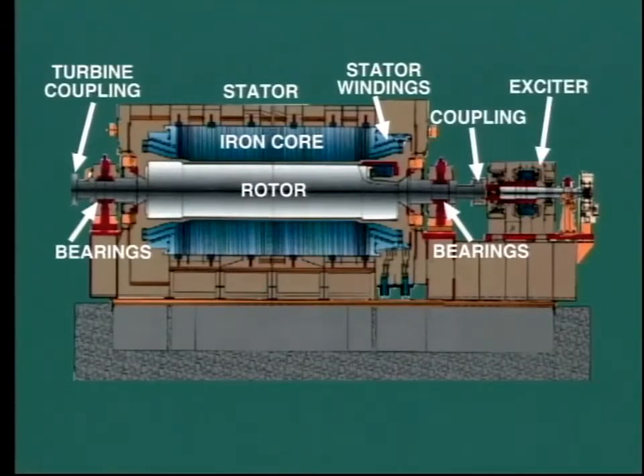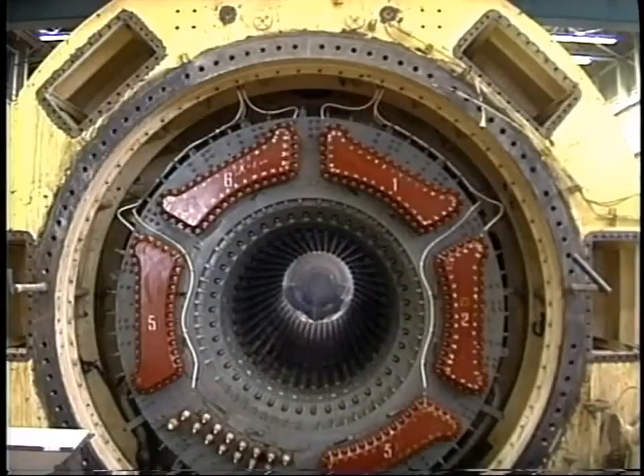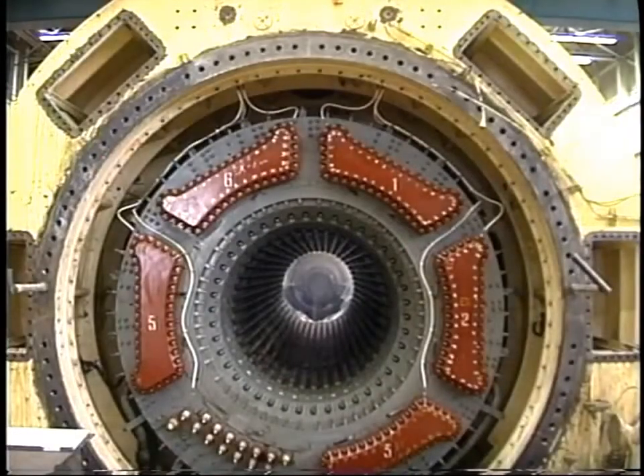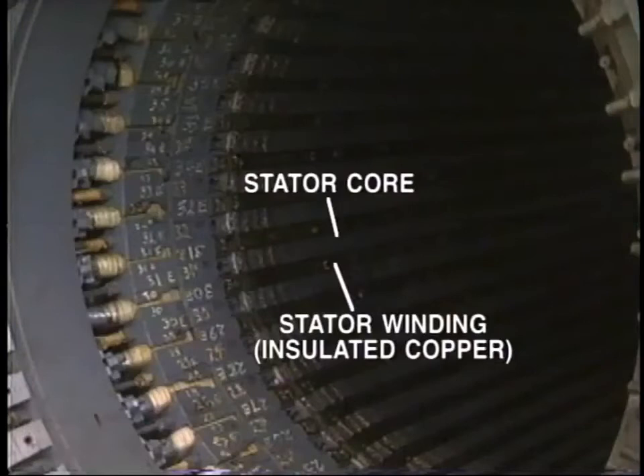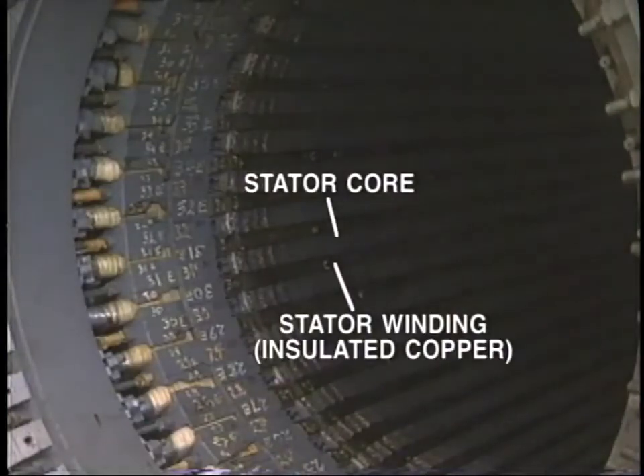The stator is anchored firmly to the concrete bed. The electricity is actually produced in the stator winding, which is the stationary winding supported by the stator frame. The stator winding consists of insulated copper conductors which are embedded in the slots of the stator core.